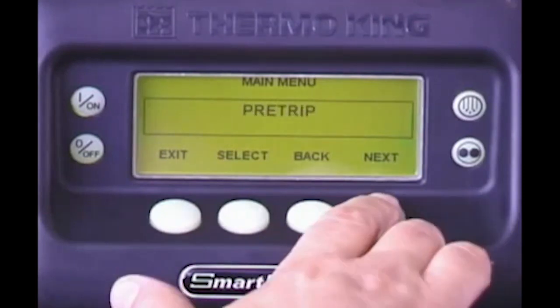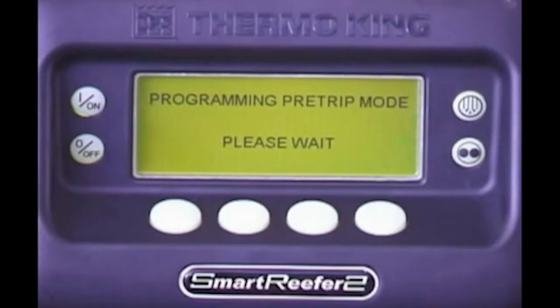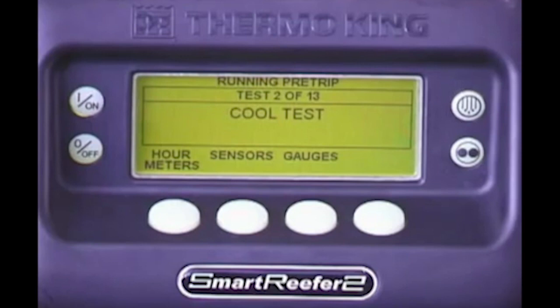Press Next repeatedly until pre-trip appears. Press Select. Programming pre-trip mode indicates the pre-trip is being initiated. Once initiated, a series of tests will be performed to verify proper unit operation. When the pre-trip is complete, pre-trip pass should appear, indicating the unit passed the test. Press Exit to return to the standard display. If pre-trip check or pre-trip failed appears after the test, contact your ThermoKing dealer for assistance.